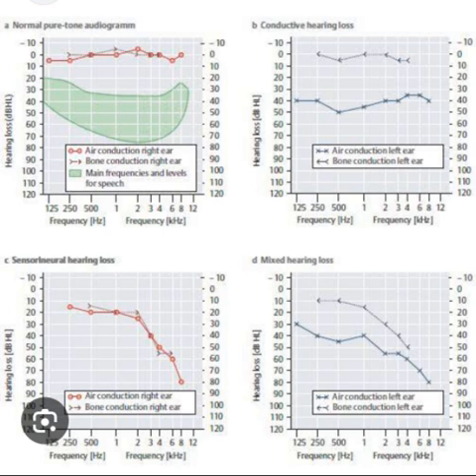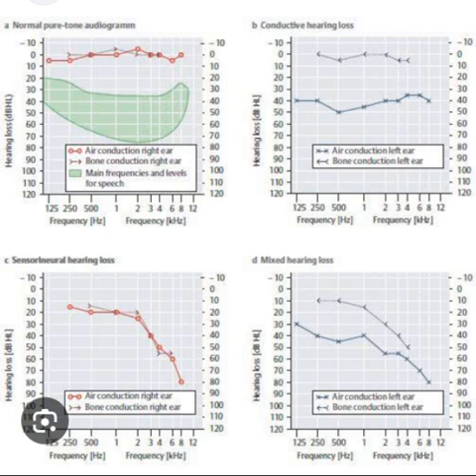Several interfering factors may complicate audiogram interpretation. First, a poor fit of earphones may cause sound leakage, invalidating results by preventing reliable independent testing of each ear. Second, if masking is not employed when indicated or the masking level is insufficient, inaccurate results may be obtained. Third, audiogram validity depends on the patient's ability to accurately and consistently indicate when they hear sounds; in functional or non-organic hearing loss, patients may report inability to hear a pure tone even if their auditory system is structurally intact.